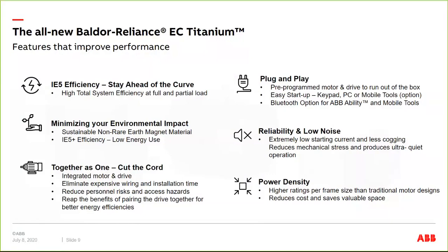So together as one, cut the cord, we integrate the motor and drive together, and that makes for a plug-and-play package, meaning that we do all the programming at the factory for you. When you take it out of the box, it's basically ready to run with a start-stop command and a speed reference. They're fully programmed and set up. There's no tuning you have to do, etc. The only reason you would get into and do programming changes is if you wanted to do the control from somewhere else, maybe adjust the accel and decel ramps or etc. But you can literally take it out of the box and it's ready to run with just a simple speed reference and a start stop.